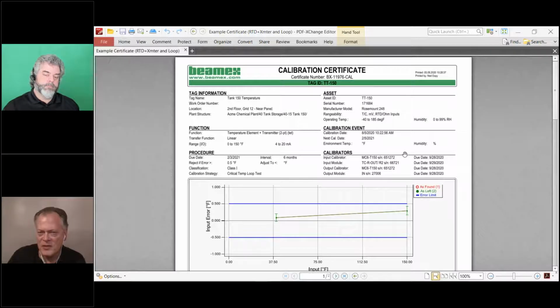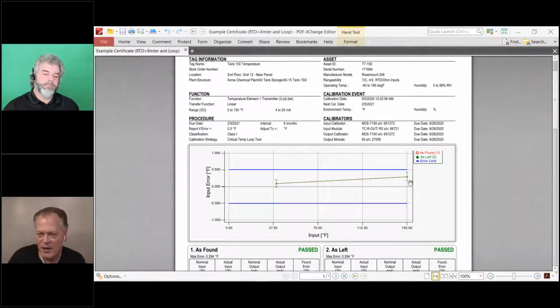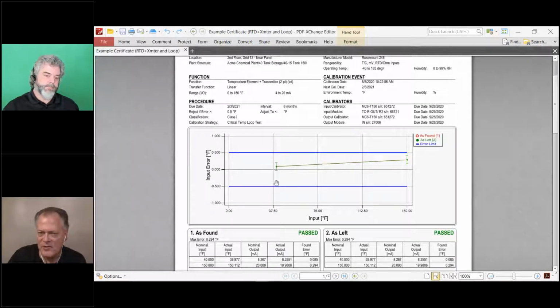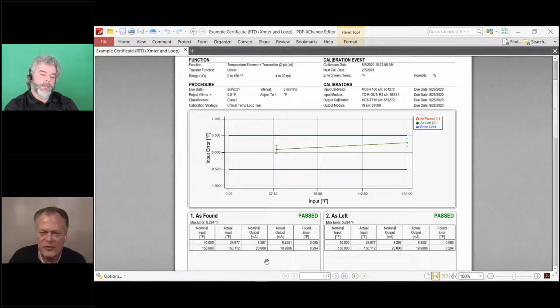In fact, here's an example certificate of what you just saw. I mentioned earlier, this half a degree is really tight. This little guide here at 0 and 100% shows how accurate the calibrator with the test probe is. You can see we have about a 4 to 1 ratio here. The calibrator standard is 4 times more accurate than this half a degree. So this is really pushing limits. And that's a visual representation of the uncertainty of the test standard.